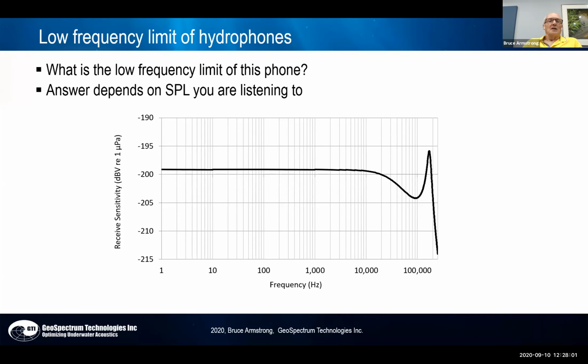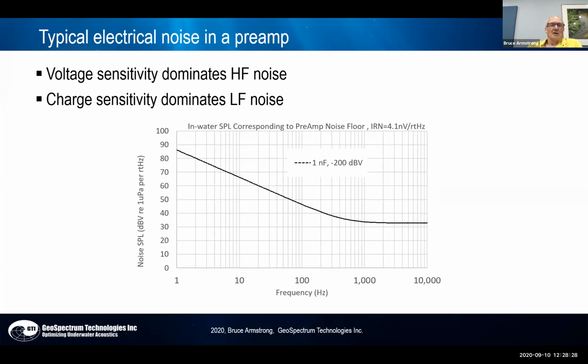So the next topic is, what is the low frequency limit of a hydrophone? If I show you this calibration curve, I could have written it down to 0.01 hertz if I wanted. Is that a 0.01 hertz hydrophone? The answer depends on how loud the sounds are that you're listening to. The hydrophone will operate properly at 0.01 hertz, but is that going to be of any use to you? The answer is, it depends on the noise in your preamp.